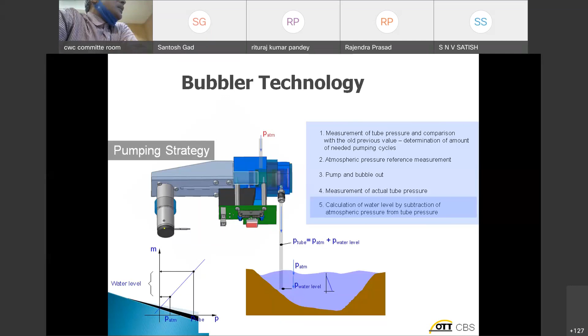Here, as you can see, this is the graph in which you are getting the calibration, and this is the atmospheric pressure and tube pressure. The difference of this will give you the water level. All this calibration will be automatically done at the time of installation. This has to be recalibrated whenever there is any change in the bubbler or you are replacing the bubbler tube and other things. Accordingly, you have to calculate and recalculate and keep it the latest.